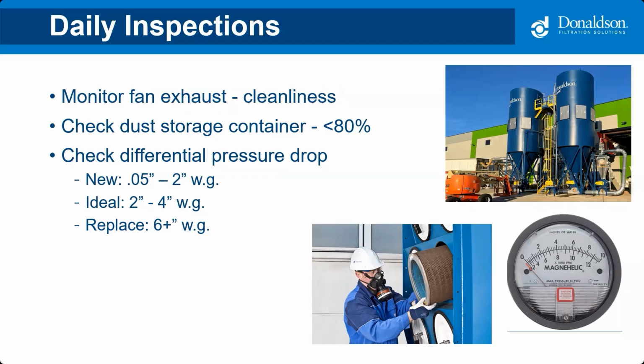That's pretty normal. And then finally, if you start seeing those filters are getting above 6 inches of water of differential pressure, and most importantly, after a pulsing cycle, they're not pulsing back down to that 2 to 4 range, that's a great indicator that, okay, your filters are now loaded to a point where you need to replace them. Again, these are just general rules. You'll want to check with your individual manual and your dust collector design. But in general, this is how a lot of systems are set up.